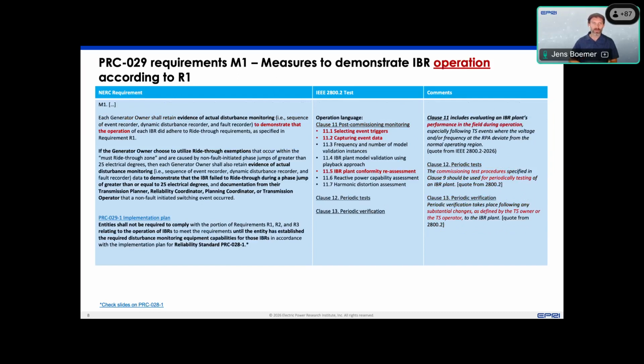And in terms of operation, measure 1 requires demonstrating that the operation adhered to the ride-through requirements, including any tripping, meeting some of the exceptions that the standard had specified. In that case, the language from 2800.2 related to post-commissioning monitoring in clause 11 also provides guidance on selection of event triggers and capturing event data, and it includes clause 11.5, which is IBR plant conformity reassessment. So if any event is caught and an unexpected behavior is observed, then this subclause can help reassess the conformity with IEEE 2800 and therefore, to a large extent, also PRC 29.